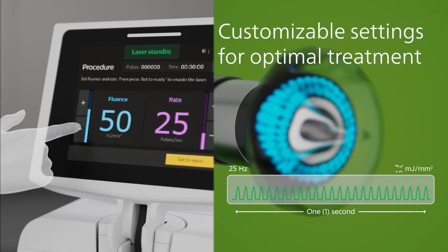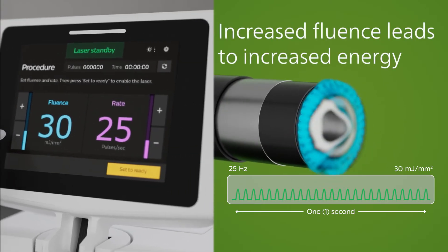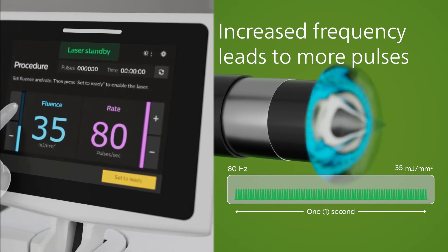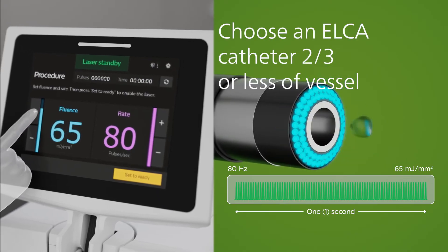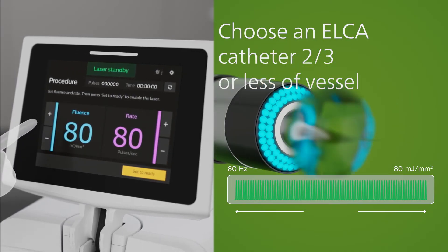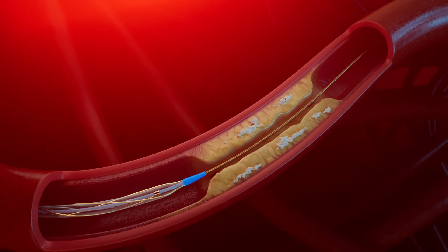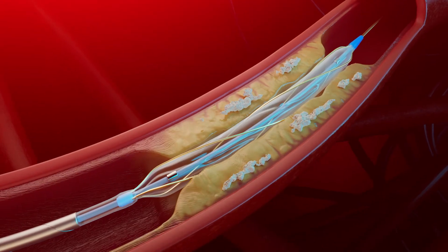ELCA has customizable energy and frequency modes to effectively debulk different morphologies. Fluence is the energy that is created during photoablation. Rate is the number of times per second the three mechanisms of action occur during photoablation. At max fluence settings, the cavitation bubble will be approximately 50% larger than the tip of the catheter, maximizing debulking. With slow and repeated advancements of ELCA, you can optimize your luminal gain. Once a channel is created, you can continue prepping your vessel for optimal treatment.